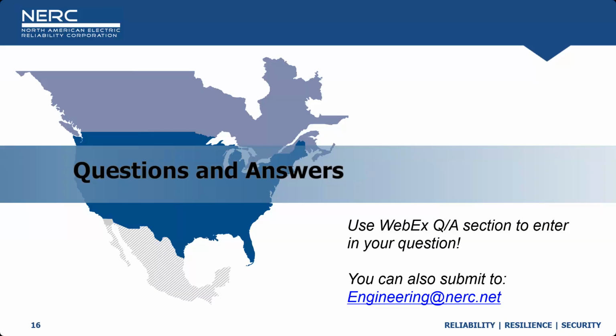Over to you, JP. Thanks, Hasla, I couldn't agree more. Past NERC engineering studies have looked at various ways of handling ride-through, not specific to data centers, but generally found that ride-through wasn't the only option for on-fault and post-disturbance recovery. However, transmission stability needs to be maintained throughout those periods, and there are different methods to accomplish that objective. Making sure those are well identified, especially in areas of highly coincident load sensitive to voltage excursions, is heavily important.